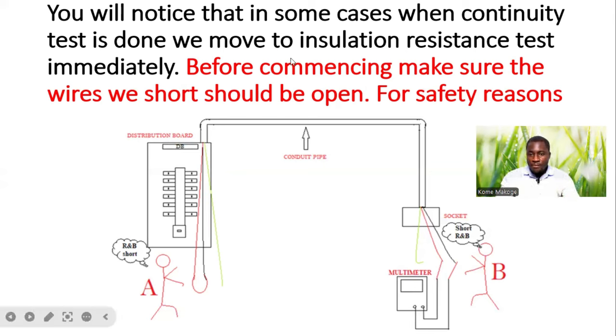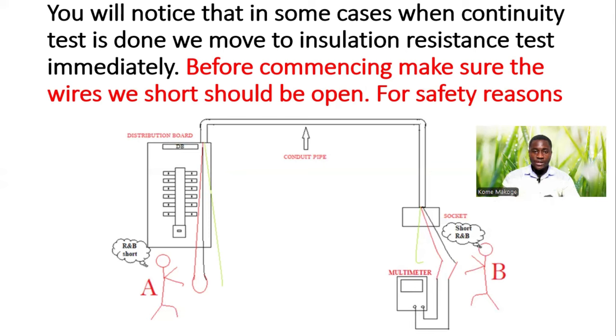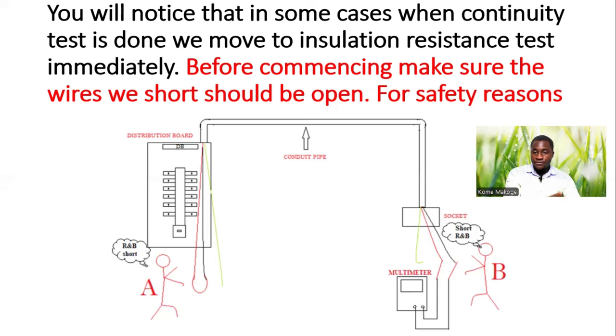Before commencing, make sure the wires that were shorted should be open. Because while we are carrying out continuity test, we have to short one end and then test the other end. So after that test has been done, if we are going straight to perform insulation resistance test, we have to ensure that we open the end that was shorted previously while carrying out continuity test, before carrying out our mega test.